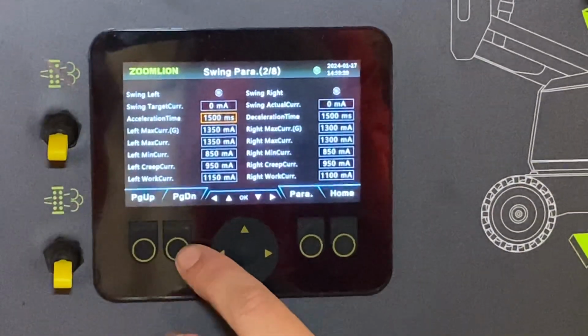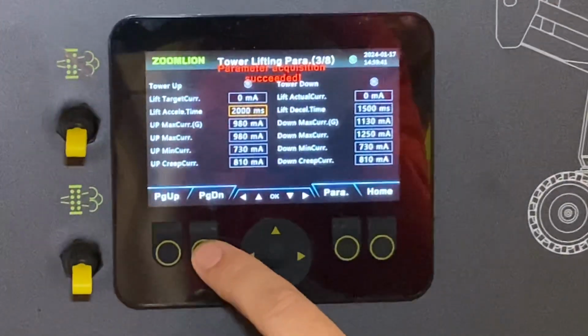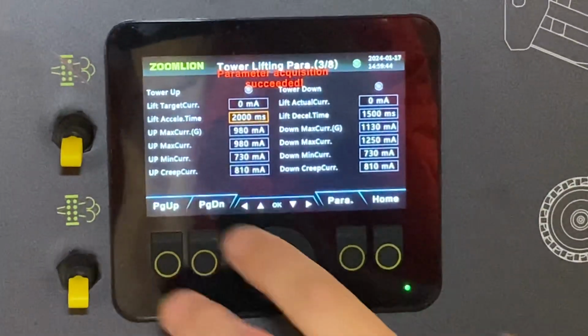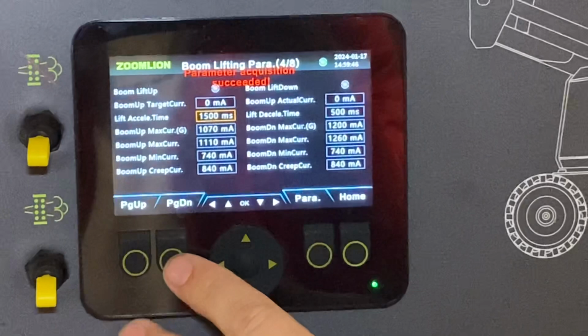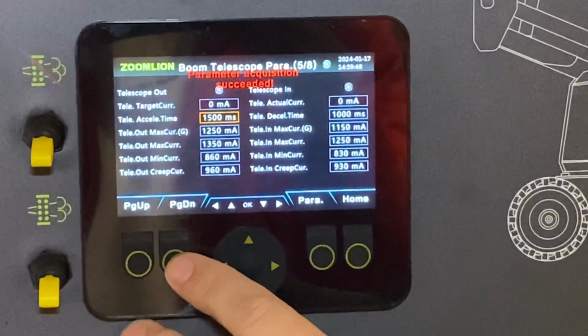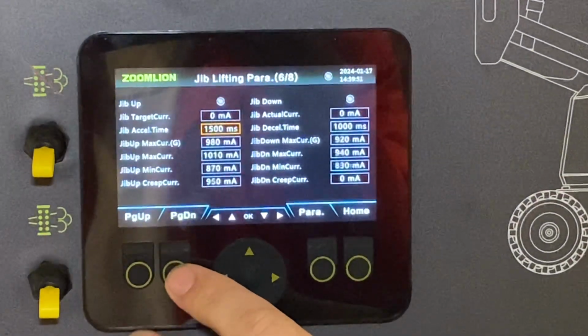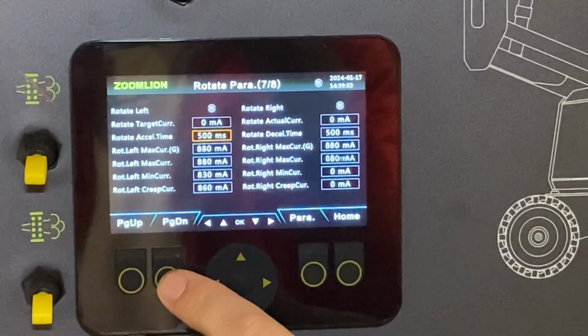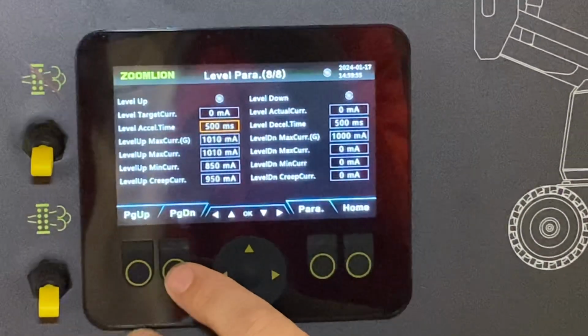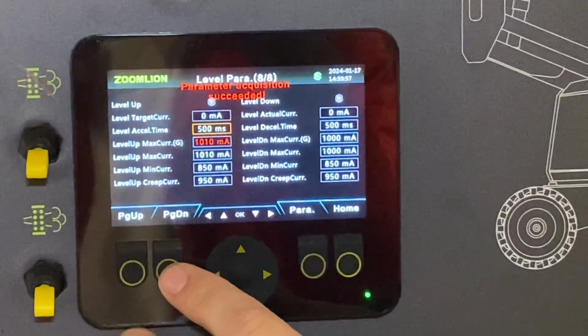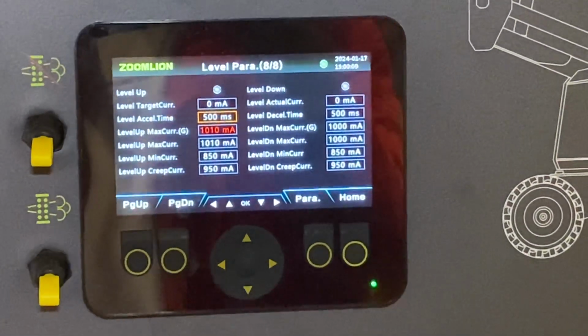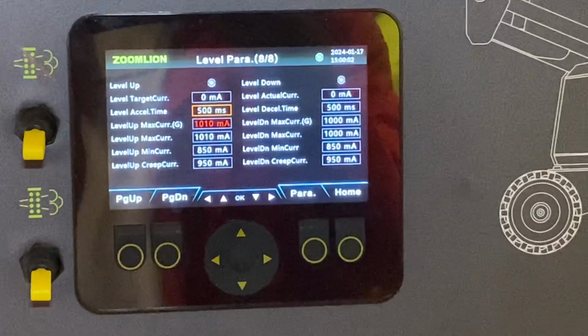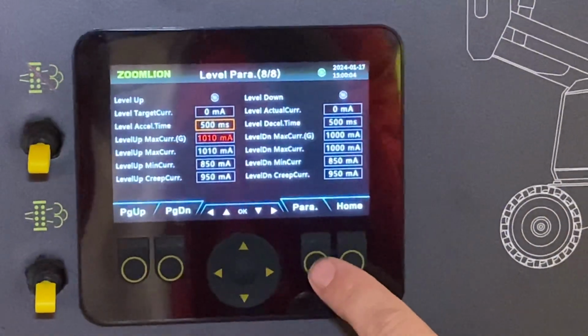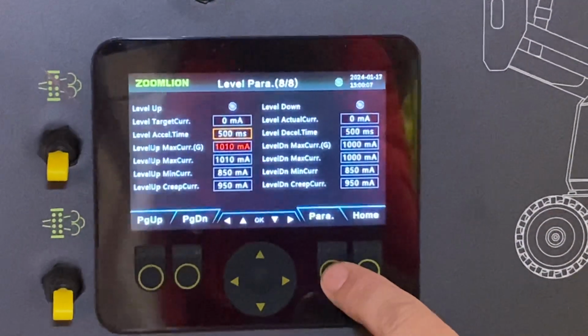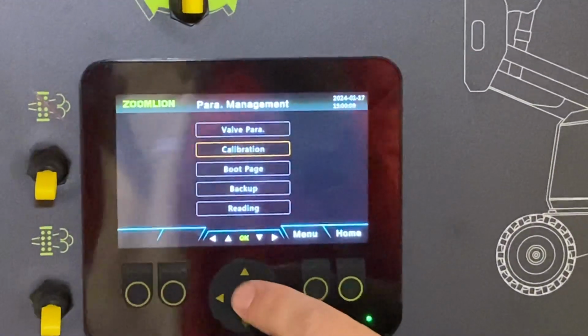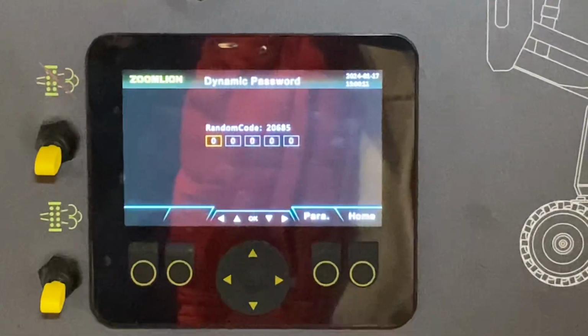Okay, so you can see here, if we page down, we have the tower lifting parameters, exactly the same format. Boom lifting parameters, the same. Boom telescope parameters, jib lifting parameters, and rotating parameters, and then gauge level parameters. Okay, so this is how we fine tune the acceleration, deceleration times, maximum, minimum, and creep currents for all boom and drive functions. Okay, so now we'll go into the calibration menu to see what we can do in there.